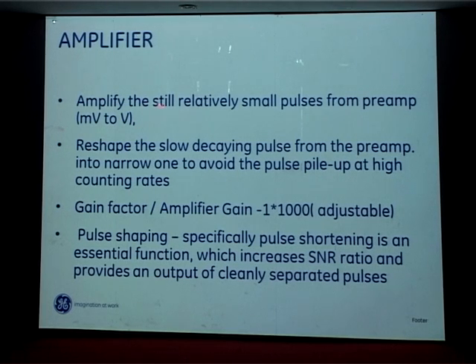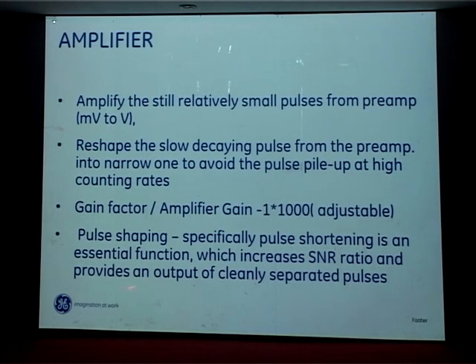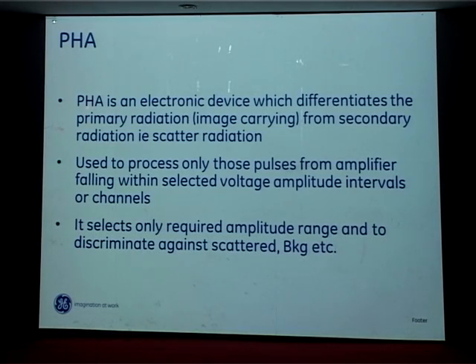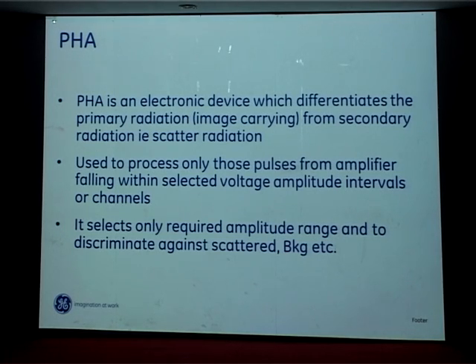The amplifier further amplifies the signal from millivolts to volts and reshapes the slowly decaying pulse. Pulse shaping is an essential function that increases the signal-to-noise ratio and provides an output of cleanly separated pulses. The pulse height analyzer (PHA) is an electronic device that differentiates primary radiation from secondary scattered radiation. It retains only pulses of a particular energy and cuts out scatter, which would otherwise degrade image quality.